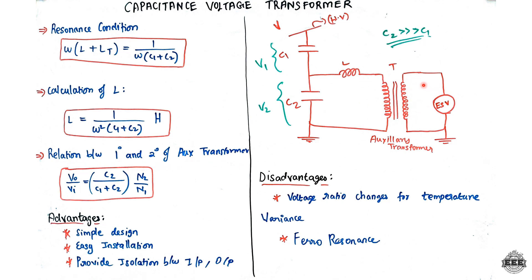The output and input relation is V0 by Vi equal to C2 divided by (C1 plus C2) into turns ratio N2 by N1. The main advantage is simple design - it is easy to design and install. It also provides isolation between input and output. The main disadvantages are ferro-resonance, as well as voltage ratio changes with temperature. Thanks for watching, bye.